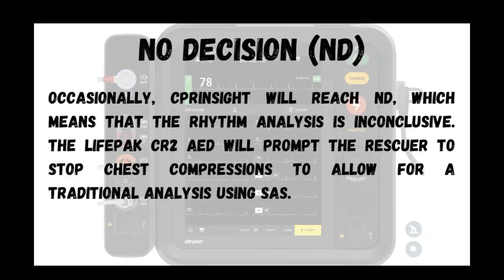And then the last is no decision, or ND. Occasionally it will reach an 'I'm just not sure' — ND — which means the rhythm is inconclusive. It will prompt the rescuer to stop chest compressions to allow for a traditional analysis using SAS if we're talking the CR2, or if we're talking the 35, it's the provider themselves. If it's in manual mode, if it's in analyzed mode, then again it would function like the CR2.